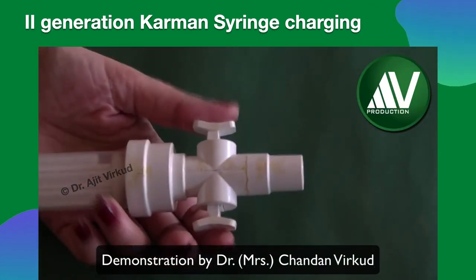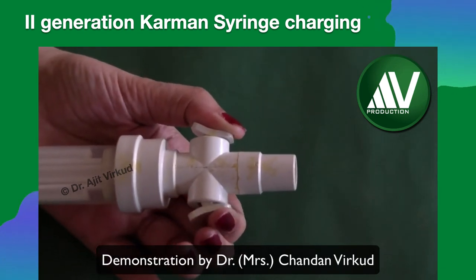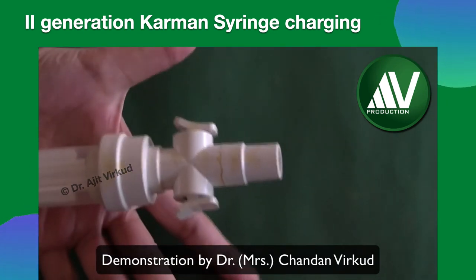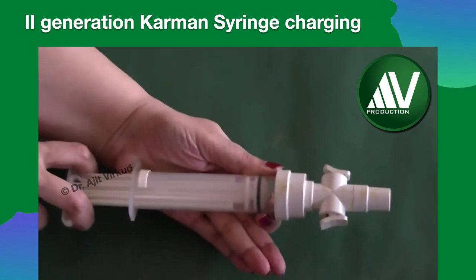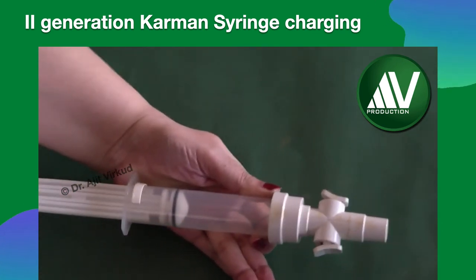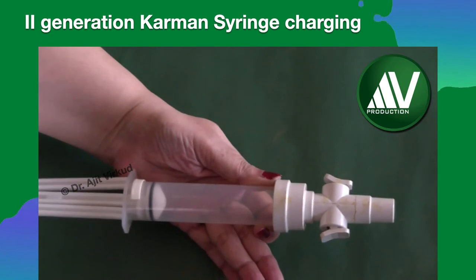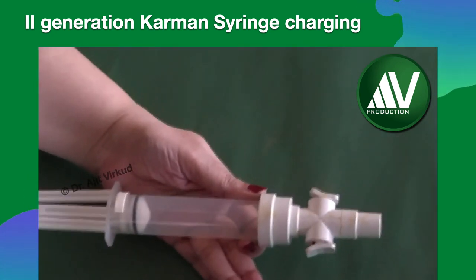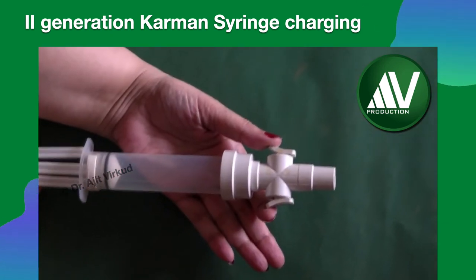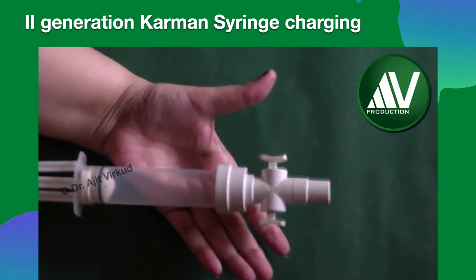I am going to show a video of how to charge the syringe, that is, create vacuum. Push the valve buttons down and forward until they lock. Then pull the plunger back until the arms or flanges snap outward and catch on the cylinder base. This charges the instrument. Check vacuum by leaving the instrument in the charged position for 2-3 minutes, then release the buttons. A rush of air indicates that the aspirator maintained vacuum.